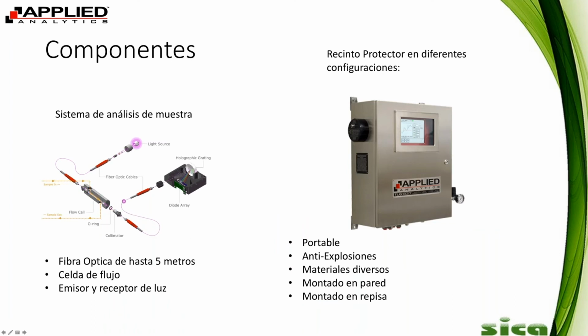But so you have the xenon light source, which is 5-year lifespan. And that goes into the fiber optic cables, and it hits the collimator, which focuses the beam through the flow cell where it interacts with the sample. And the diode array, which is basically your detector. So you have the xenon light and the diode array in your spectrometer. Then you have the flow cell, and your fibers connect those.